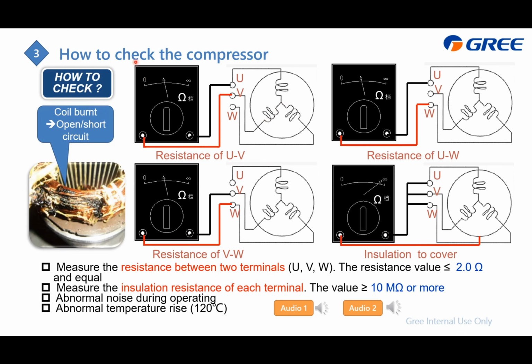So use the multimeter and change it to ohm. And then measure U to V, U to W, V to W, which are these three coils. The value should be less than 2 ohm. And also the next is to check the isolation resistance of each terminal, which is each terminal with the earth. And this value should be more than 10 mega ohm.